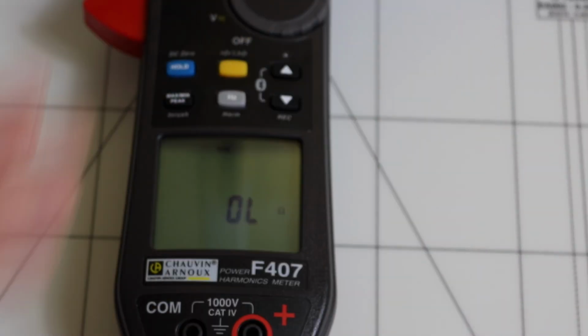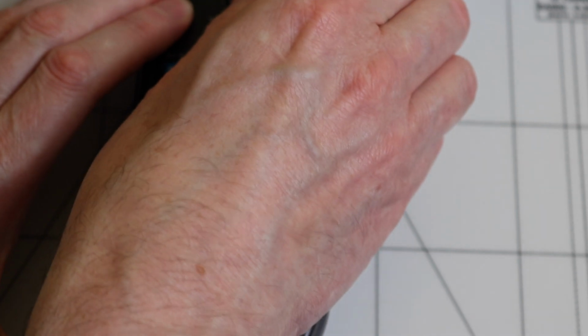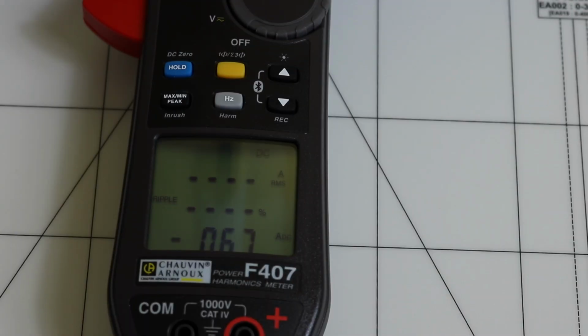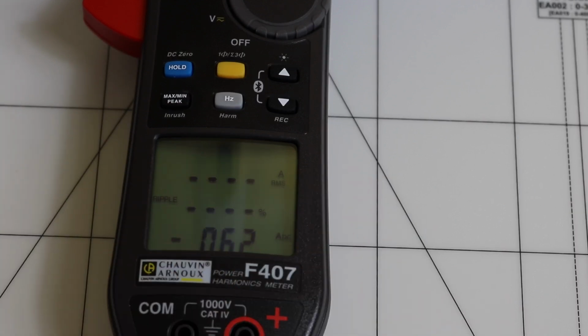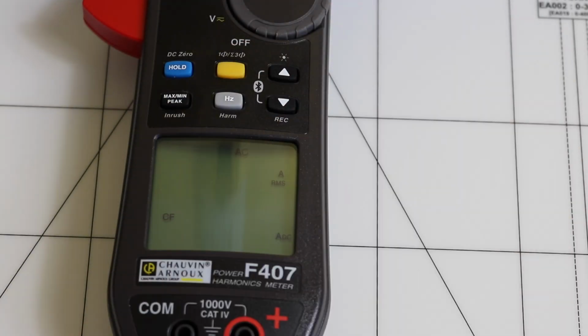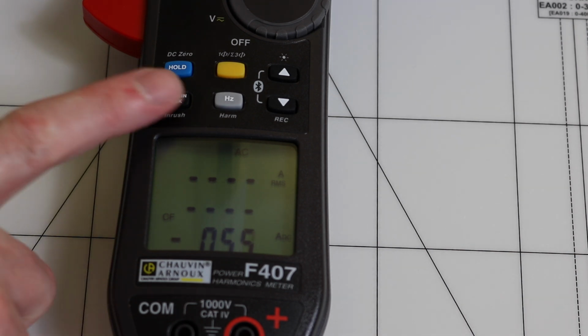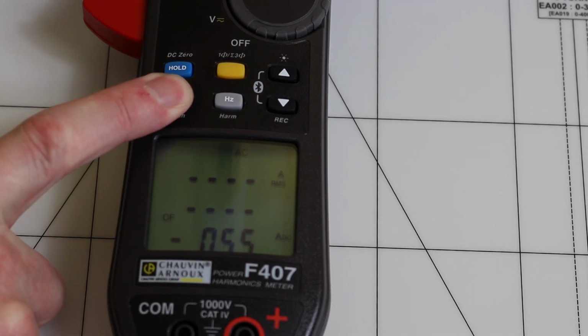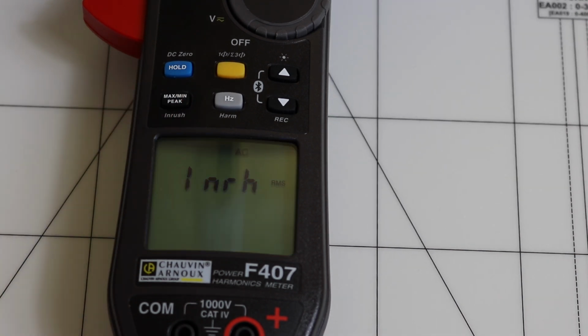Just turn it back to one of the ranges and step back up onto the amps. So to get to the inrush function itself, you select either AC or DC amps depending on which you want. I want to go to AC, and then we hold down the inrush function until AC flashes away. It's trying to detect what the current is now. Because everything's switched off and it doesn't see any current, it's actually settled on a 10 amp setting for the trigger level.